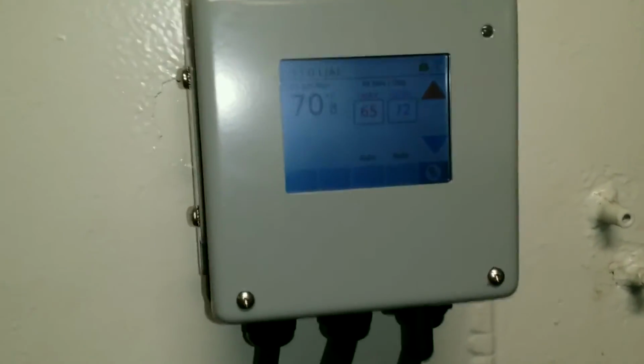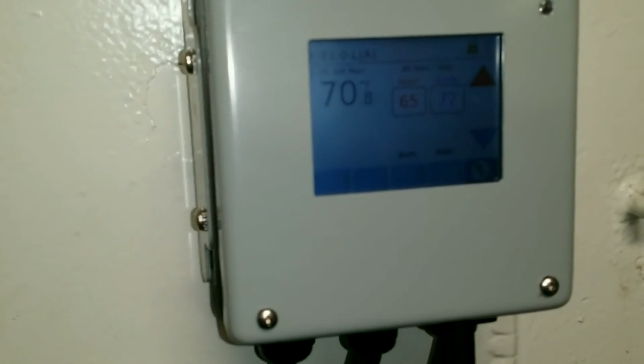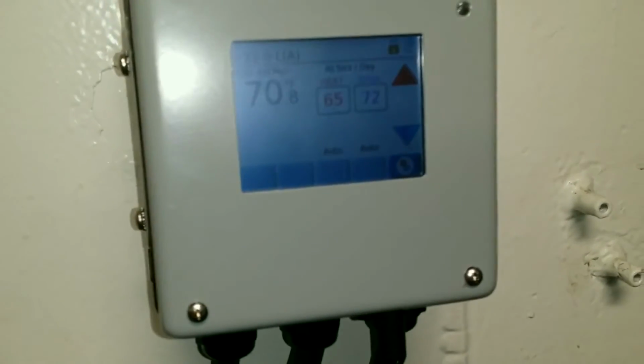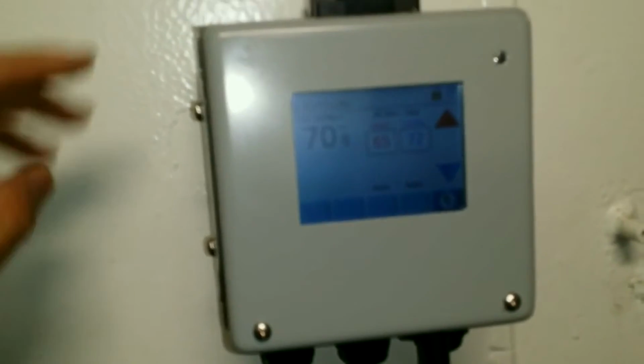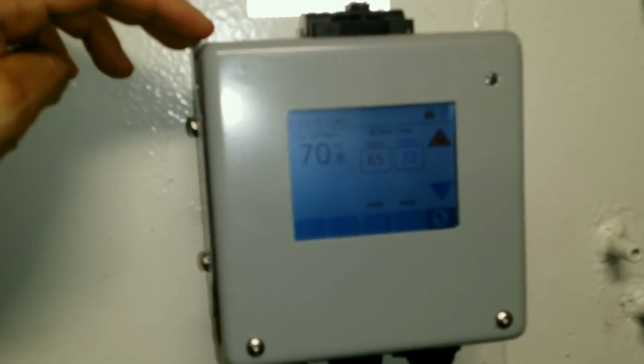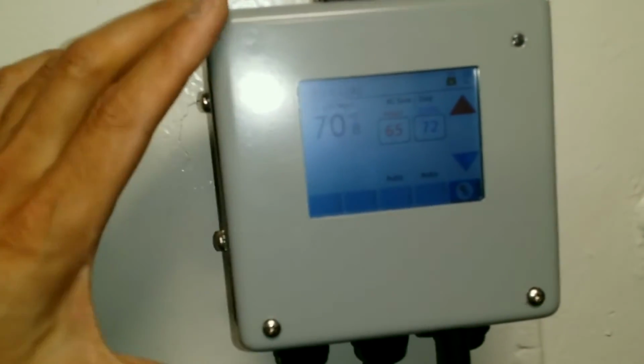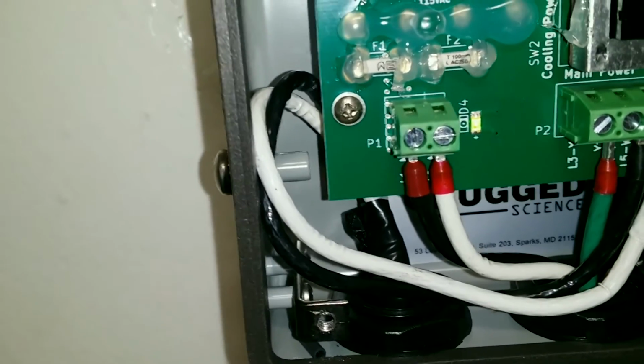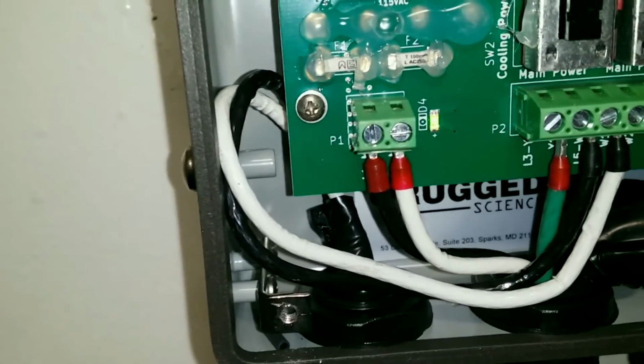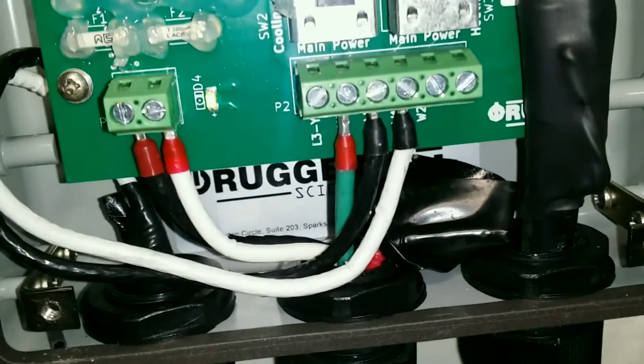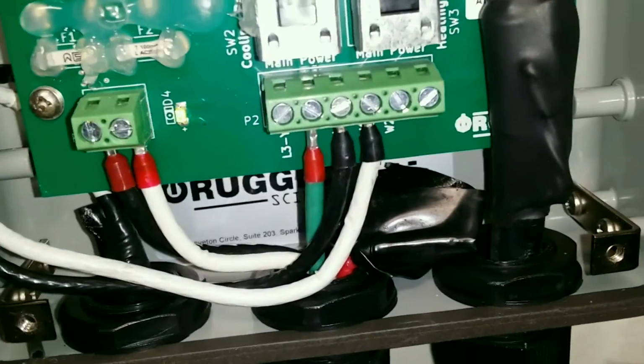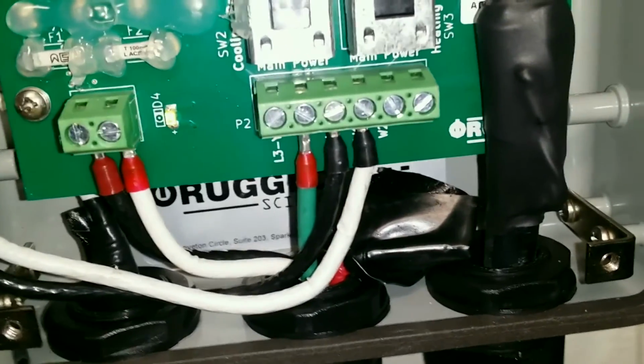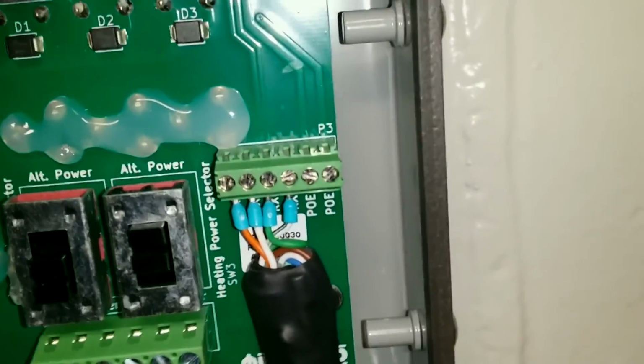The new thermostatic switches give you more information than the ones before. And they actually have a network cable that lets a monitoring system know what the current temperature of the space is. Inside you find three cables because this is powered on. This gets 110. This over here, we've got our common, one to energize the cooling coil and one to energize the heater. And then that is our network cable.